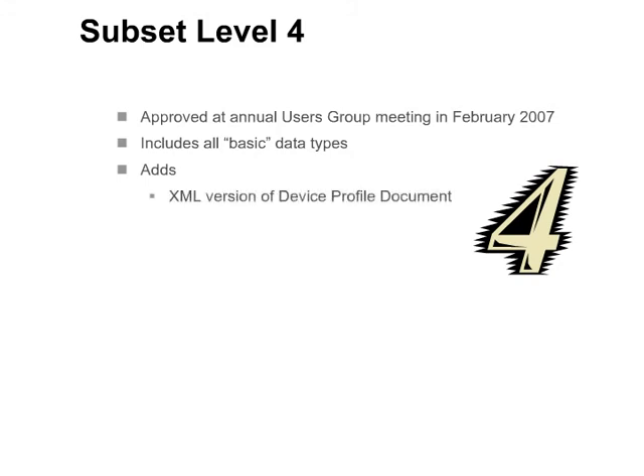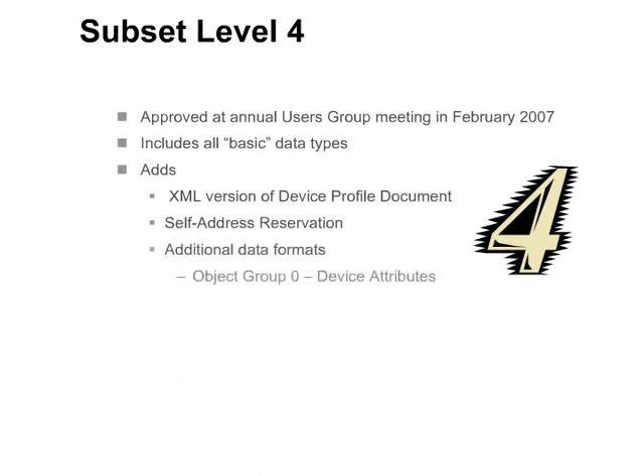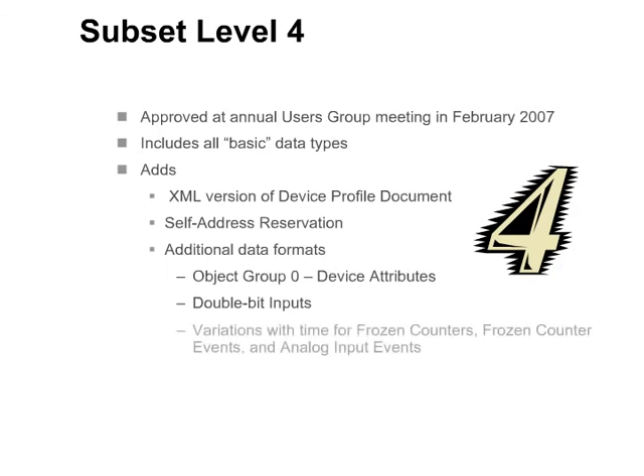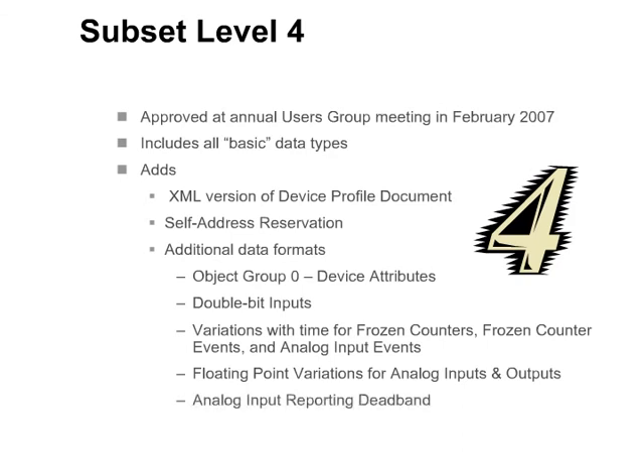Level 4 also adds self-address reservation. With self-address reservation, if a device receives a message with a destination address of hex FFFC and the self-address feature is supported and enabled, it should respond normally with its own source address instead of FFFC. Subset level 4 also adds additional data formats, including object group 0 device attributes, double-bit inputs, variations with time for frozen counters, frozen counter events, and analog input events, floating point variations for analog inputs and outputs, analog input reporting deadband, and event objects for binary and analog outputs.